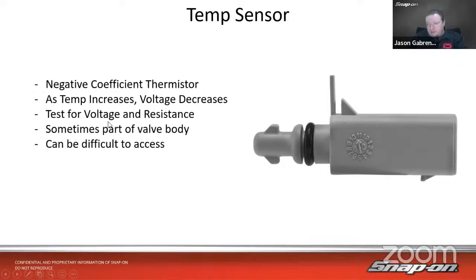You can test for voltage, you can test for resistance. So I can test the voltage going through, because the resistance changes, and that's what changes the voltage. And then we check the resistance as well. Most manufacturers will publish a table as to what the resistance should be based upon what the temperature is. Sometimes it's external, sometimes it's internal, part of a valve body. And sometimes it can be difficult to access as well. So if it is part of the valve body, that would be one of the ones where it's probably difficult to access, because internal to the valve body, you have to disassemble a lot of things.